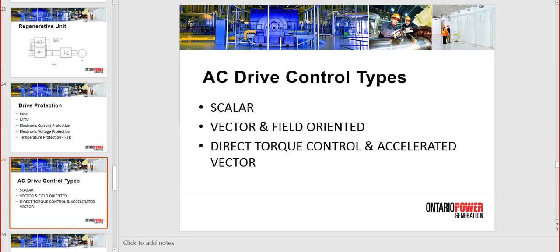Again, there is no parameter identification and there is no tuning of any regulator. It's all settings based on empirical trial and error. Easy to set up, but the scalar drive does not have torque control and does not work for harsh applications with 100% full load applied at the shaft. It will trip on overcurrent or trip on DC bus overvoltage, whatever. It cannot handle full load torque on the shaft in a step manner. Gradually, yes, on a slope or in baby steps. So that's the scalar.